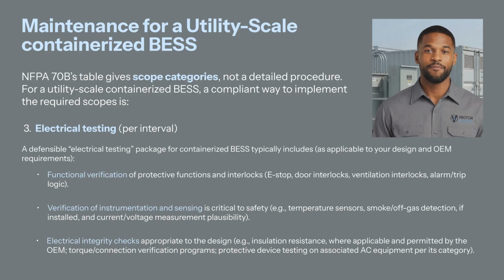Key point. NFPA 70B does not specify test methods for battery energy storage systems in its public summaries, unlike OEM manuals or ANSI NETA documents. Instead, it defines the scope and maximum intervals for testing, with the specific testing content generally based on OEM instructions and accepted practices.